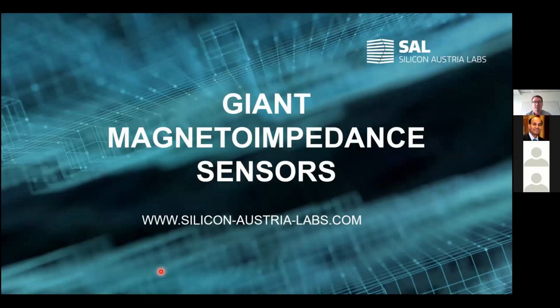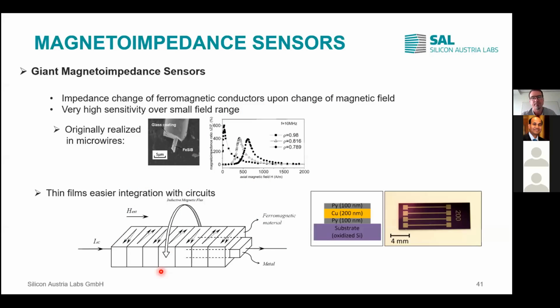This takes me to the giant magnetic impedance sensors, which are probably a bit less known, even though they are extremely sensitive. One of the best commercial sensors that I'm aware of is actually a giant magnetic impedance sensor. This effect is pretty simple, and this is probably why it is a very attractive sensor type. It was originally realized in microwires, soft magnetic microwires, typically coated with glass.